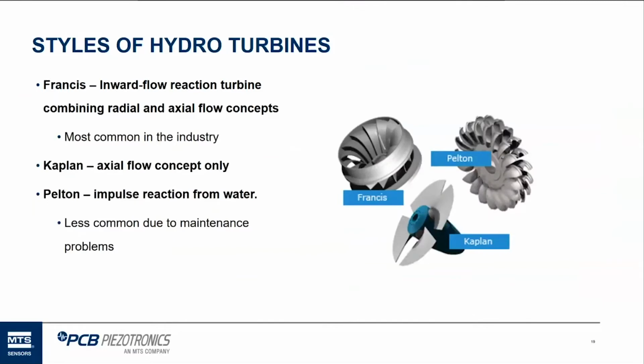Different styles of hydro turbines. Francis is the most common type of hydro turbine. It's a good part of the market. I'm not sure of the percentage, but it is the most common. It's what's called an inward flow reaction turbine, so it combines radial and axial flow. It's flow from the penstock where the water comes in, and also the pressure underneath the runner as well. A Kaplan style turbine is an axial flow concept only, so it's just the water flowing underneath the runner.